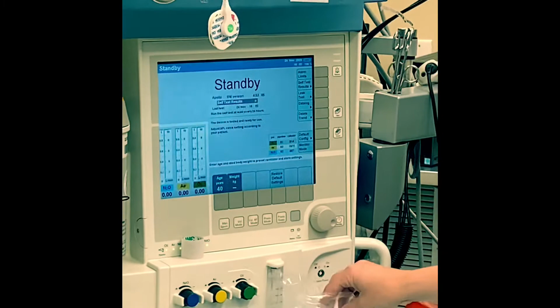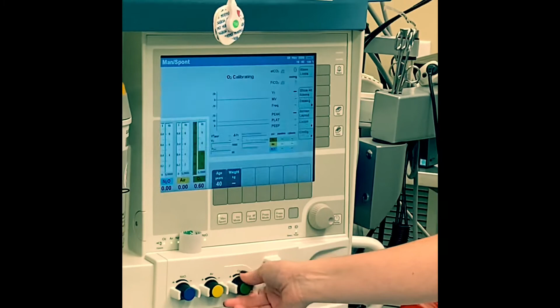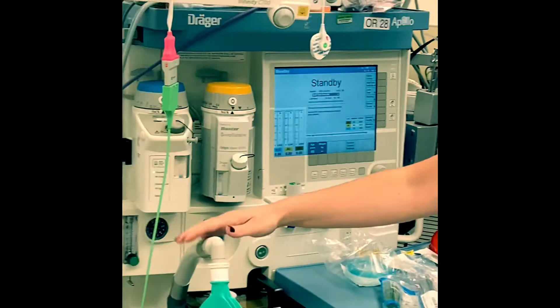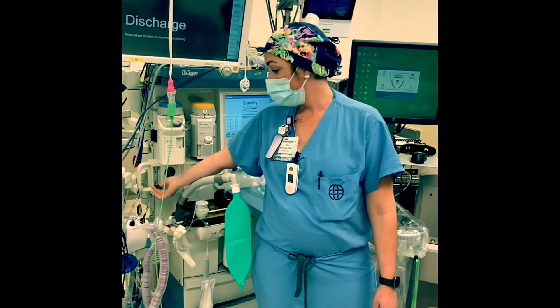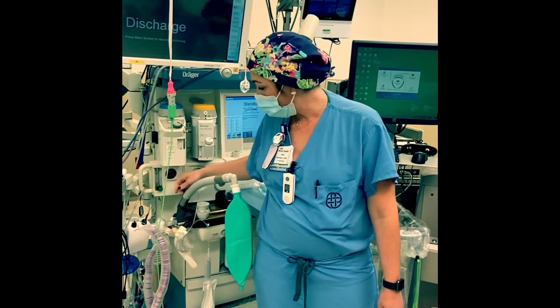96% done. We're 100% done. This is what it looks like when the machine check finishes. A couple of other things to make sure that your machine does is turn on oxygen. Make sure that it kicks your ventilator on. And you should also always know where your auxiliary oxygen flow is going to be. So turn this on, make sure you get oxygen. You'll use this if you're doing most MAC cases. So that's where that is.